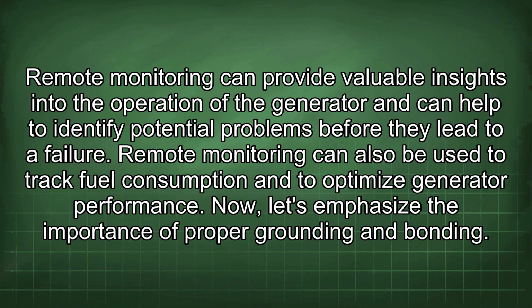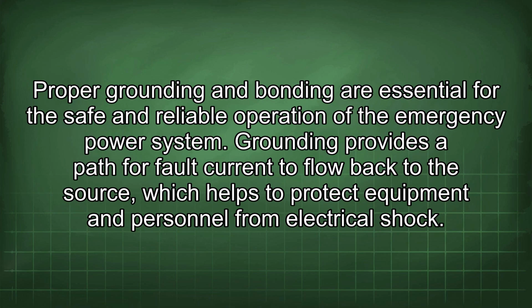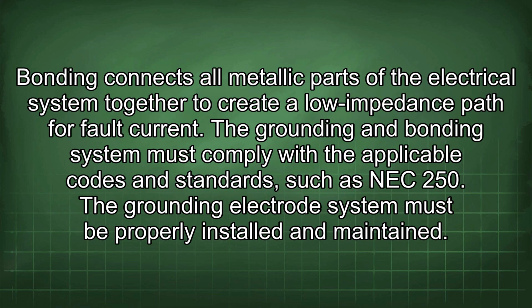Now, let's emphasize the importance of proper grounding and bonding. Proper grounding and bonding are essential for the safe and reliable operation of the emergency power system. Grounding provides a path for fault current to flow back to the source, which helps to protect equipment and personnel from electrical shock. Bonding connects all metallic parts of the electrical system together to create a low impedance path for fault current. The grounding and bonding system must comply with the applicable codes and standards, such as NEC 250.